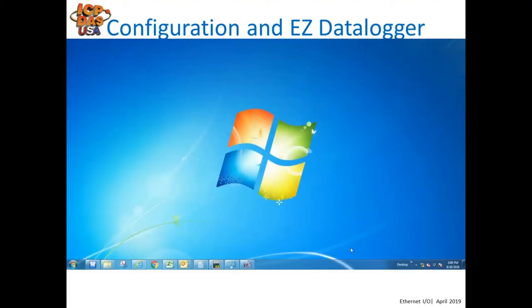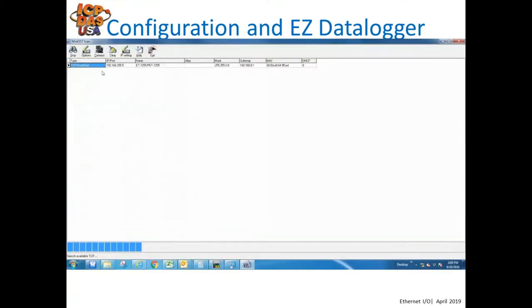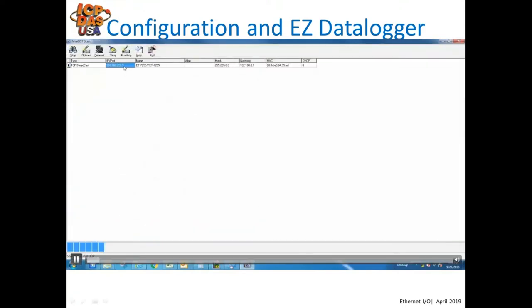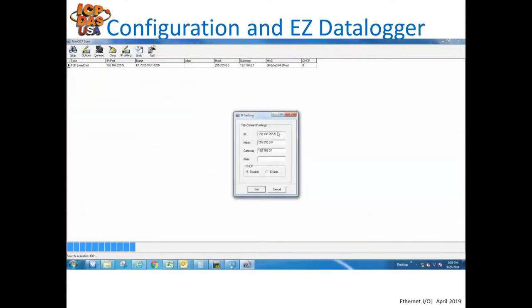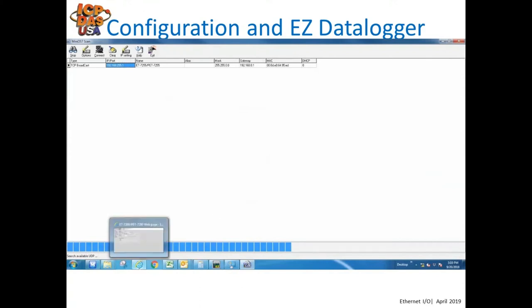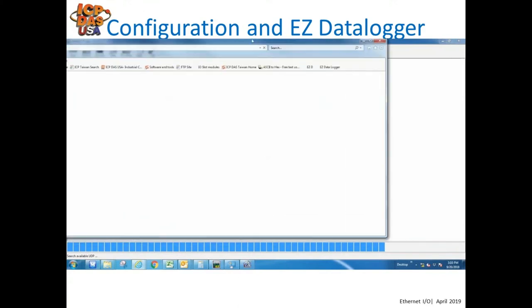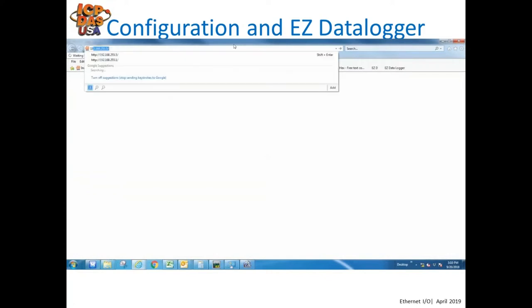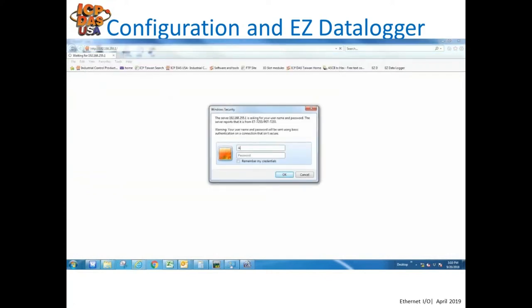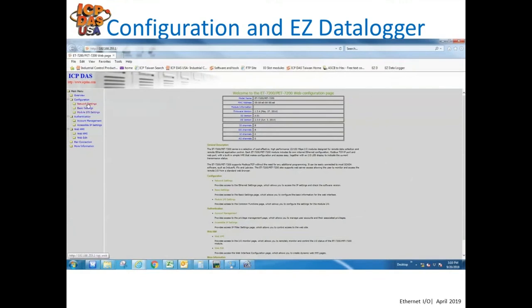This presentation includes a quick video showing how ET-7200 modules are configured and how you connect to our Easy Data Logger software. Brand new out of the box, the module comes with a static IP address. You use our MiniOS7 utility to search for the module and set the IP address — in this case, changing it to 192.168.255.1. After setting the new IP address, you open a web browser, type in 192.168.255.1, and the module prompts for a password. The default password is 'Admin' with a capital A. You log in to configure the module and view IO status.